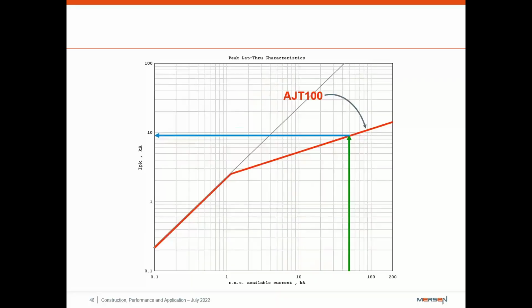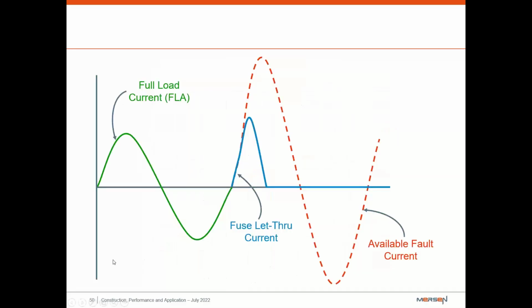Getting into the peak let-through current, and this is how much current an end device will possibly see. So we're going to have our curve, which is the AJT 100. You're going to come up from the bottom, which is going to be your RMS value, and on the left is going to be your peak. So you have 10, 20, 30, 40, 50,000 amps, come up to where it crosses the line, and it's going to be about 9,000 amps. But if you want to know what that is in RMS value, we put in this gray line, and where it comes back down is going to be the amount in RMS, so you don't have to do any kind of calculations or anything, even though sometimes that's fun. It'll be about 4,000 amps RMS.